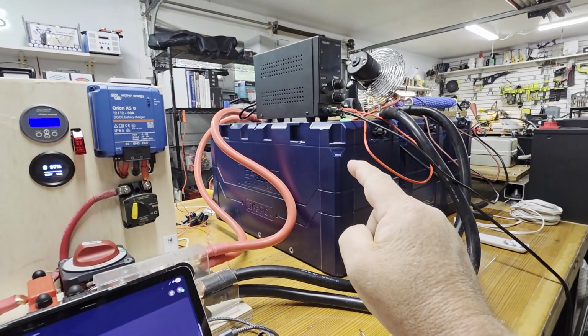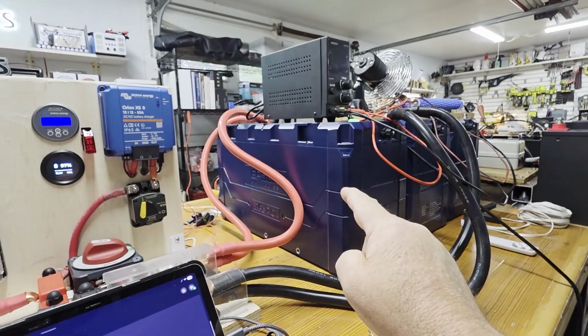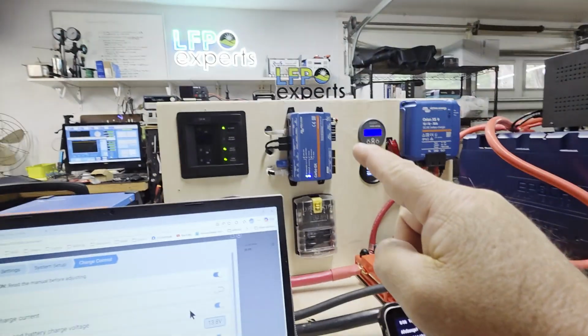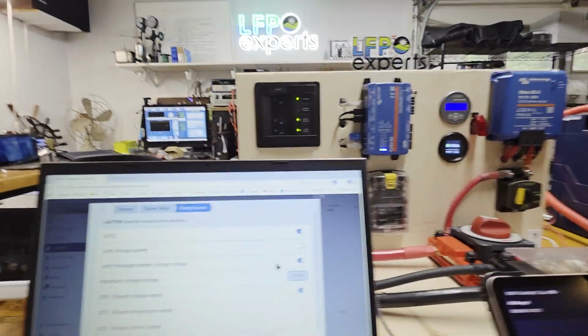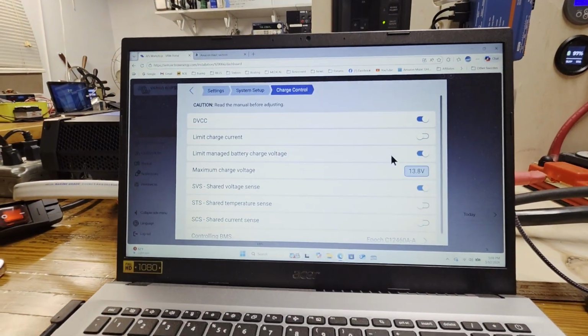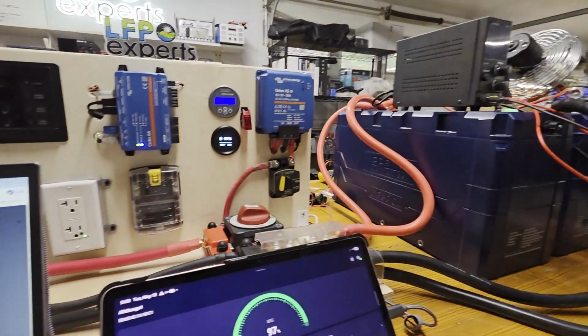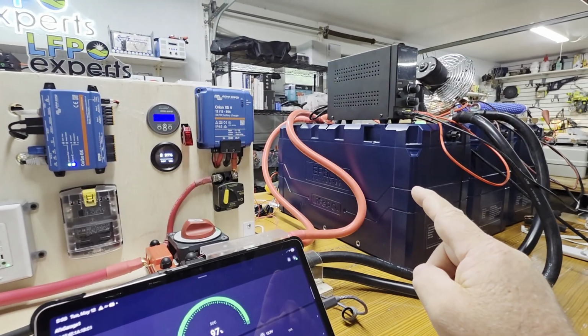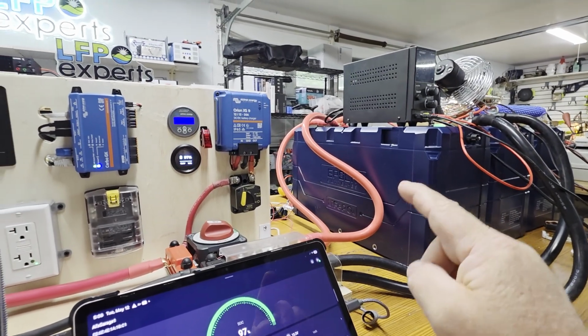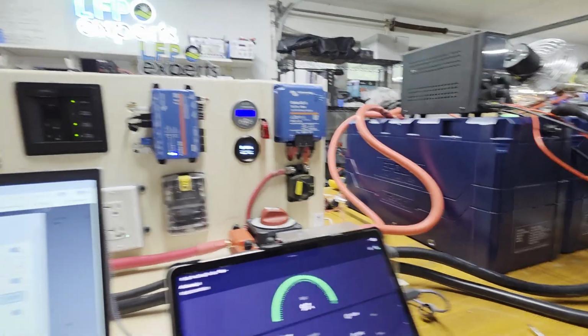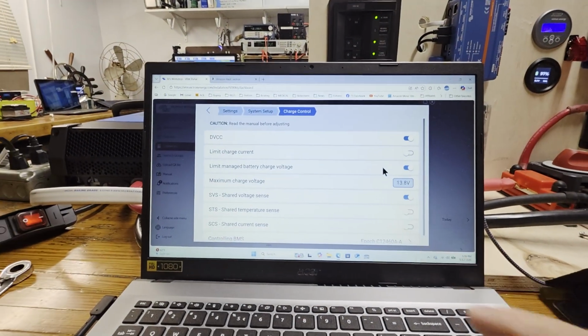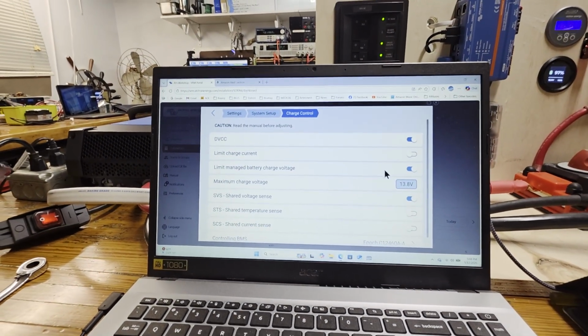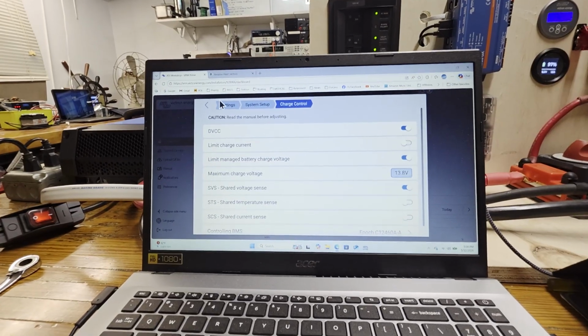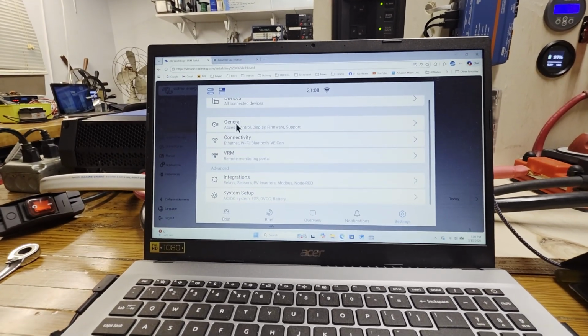Because under BMS control, the target output voltage requested by the battery to the Victron system is 14 volts, we're going to hold it slightly under 14 volts. That way, it's never going to let this shift from 14 volts absorption into the float voltage of 13.5. We're doing that because 13.5 really isn't enough voltage to get this to balance, but 13.8 is.